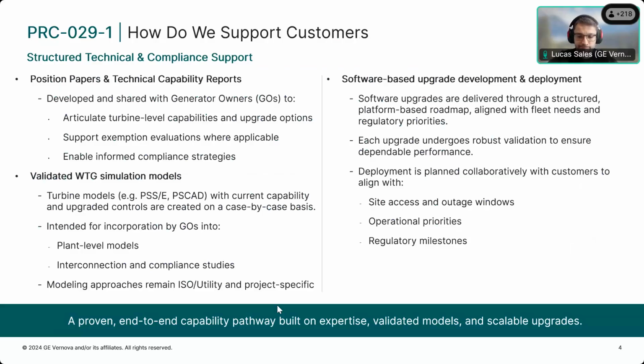Yeah, I think it's worth mentioning that multiple times we talk about requirements, and we think that moving protection settings out of the way and/or just updating control settings is enough. But the reality is that with these harsher requirements, which especially the legacy platforms weren't originally designed for, moving protection settings out of the way isn't enough. So multiple times this requires the OEM ourselves to revisit the original control strategies, assess, let's say, damage curves, and in some cases actually create new control features that would allow us to ride through these expanded or harsher requirements. And in most cases, we are able to do that with a software upgrade only.